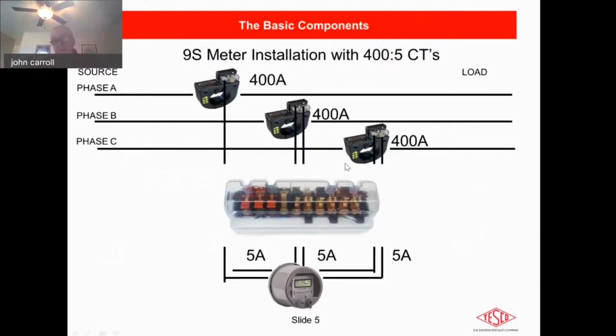So, basic components. Most people who've dealt with this type of environment before will be familiar with these. These are typical; there's a lot of this type around. This is a current transformer. In this particular case, we have 3 phases. It's a 9S installation, so we have 3 CTs, in this case a 400 amp service, or 400 to 5 is what the ratio is on their nameplate. And you can see it goes through a test switch, which of course TESCO make very well.